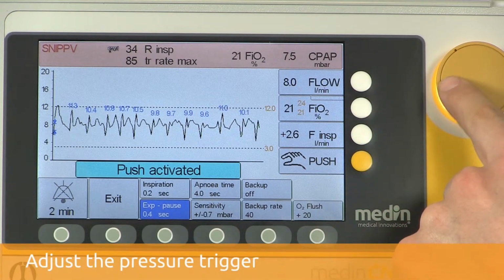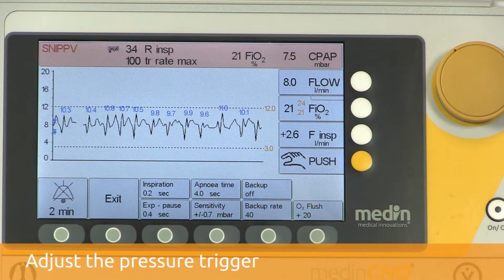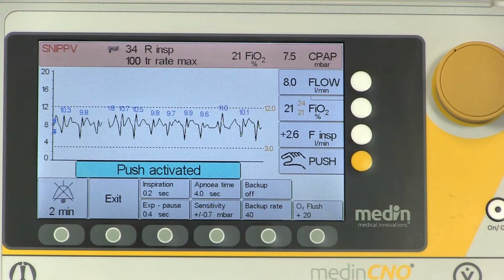To adjust the pressure trigger correctly, the pressure fluctuations during spontaneous breathing have to break through the trigger thresholds, marked here with blue arrows.